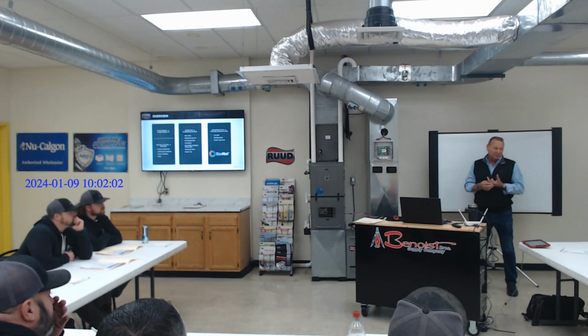The days of walking in and looking at a furnace and going, well, it worked for 20 years, I'll just put that same size in here, is over. That's where we're getting into trouble. Because we're not doing loads, we're just doing a simple, oh, that worked for 20 years, and guess what? It don't work anymore. This is beyond zoning, but you gotta understand this, because when you're going to look at a zone system, I'm concerned more about CFM, and what size AC and furnace the smallest zone will handle, even if I have to add a bypass, okay?